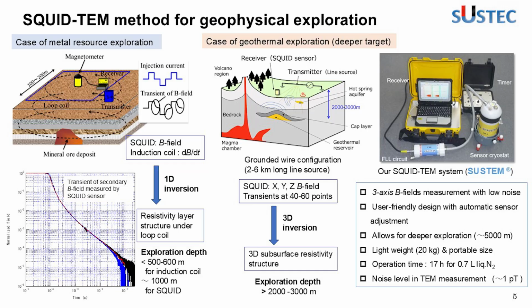Okay, this is a picture of our recent SQUID-TEM system named SUSTEM. The weight of the total system is only 20 kilograms, and one person can carry the whole system. Here, this is the sensor cryostat. The three SQUID sensors are cooled with 0.7 liter of liquid nitrogen, and we can continue to operate this for 17 hours, long enough for one-day exploration. And the noise level in TEM measurement is very small, about 1 picotesla level.